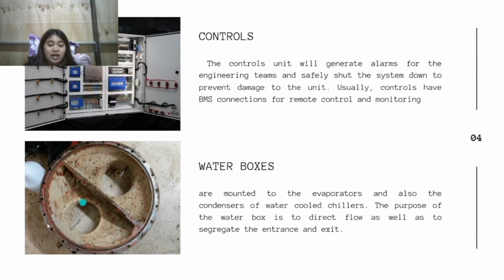So this is a water box. Water boxes are mounted to the evaporators and also the condensers of water-cooled chillers. The purpose of the water box is to direct flow as well as to segregate the entrance and exit. Water boxes are only found in water-cooled chillers.